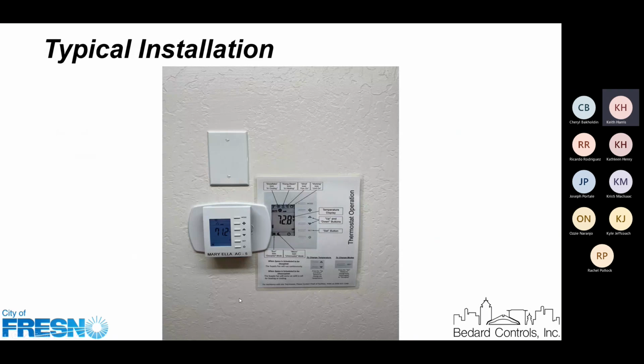Okay, this is an installation we did last week at one of the park sites. So you can see here's our instruction sheet. I bring this up for two reasons. One is we're trying to label each thermostat with a unique identifier, usually using the park name and then the equipment number. So this is Mary Ellen Brown AC-5. If you have any issues, it's really helpful if you tell us that information so that we can track it down in our system.